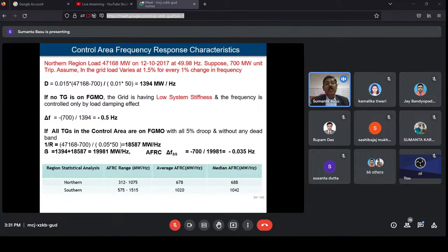Now if we see that all the generating stations in that control area are on free governor mode operation, that means no dead band, with all the machines having 5% droop, then the area frequency response characteristic comes to 0.035, and your beta factor, which is called the area frequency response factor, becomes 19,000 megawatt per hertz. As I told you, this is time variant. It is being calculated every second, not even every second, every millisecond.